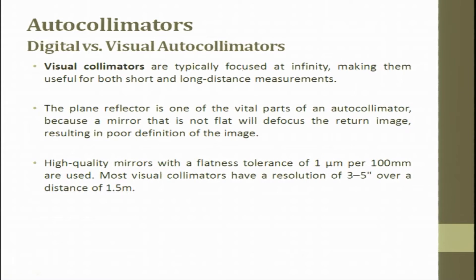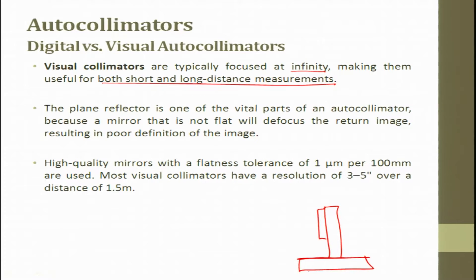The visual autocollimator is typically focused at infinity, making it useful for both short and long distance measurement. A plane reflector is one of the vital parts of an autocollimator. The mirror placed on the stand must be flat — a mirror that is not flat will defocus the returned image, resulting in poor definition. When using an autocollimator, the mirror surface has to be as flat as possible and of high precision, with a very tight flatness tolerance.